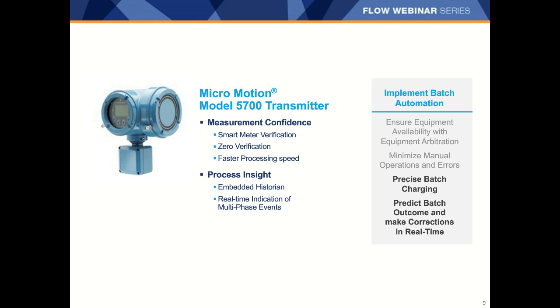Zero verification. To take the guesswork out of commissioning or reconfigurations, gone are the days of having to zero your new meter on the process before operation. In fact, the factory zero will, in most cases, be the most accurate zero the meter will have. Zero verification actually checks the block-in and process stability, and the algorithm determines, if needed, if the meter should be zeroed or not.